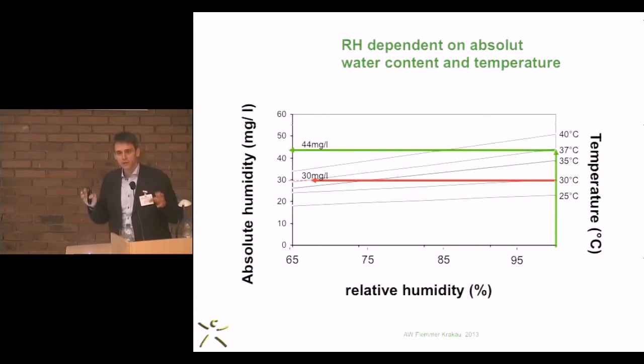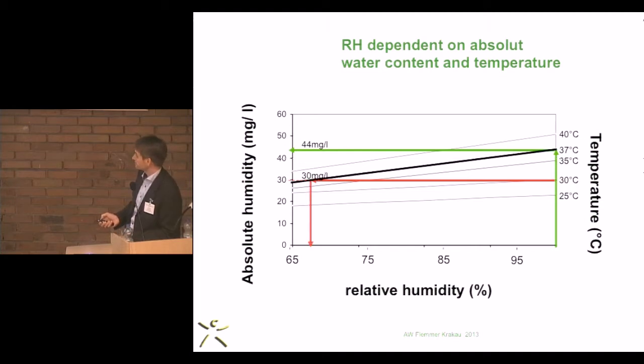So if you go back to your incubator, once again, you have to keep in mind, if you see rain out at the walls of this incubator, you're not going to have the humidity you want to achieve, and your digital numbers show you it's no longer 80% or 60% or 70%. You're losing a substantial amount of humidity if you have rain out. And you only can increase the humidity again if you add water. Okay? And the same is true for the conditioned gas in our tubing system until it reaches the child. Now again, if you reheat, you're going to be down at 65%.